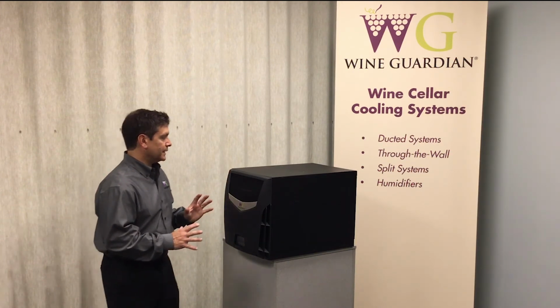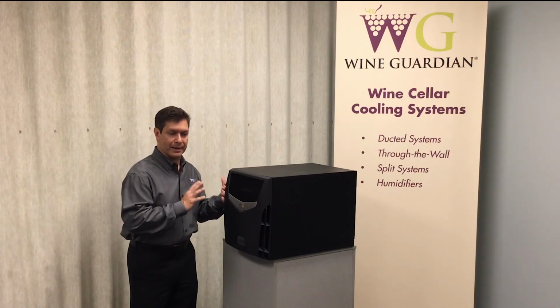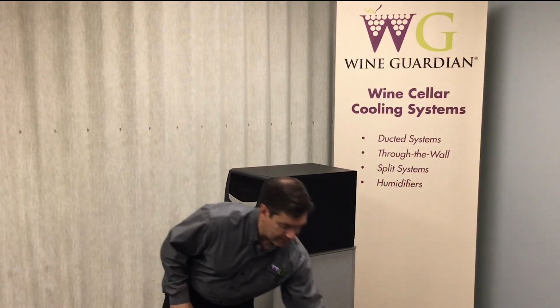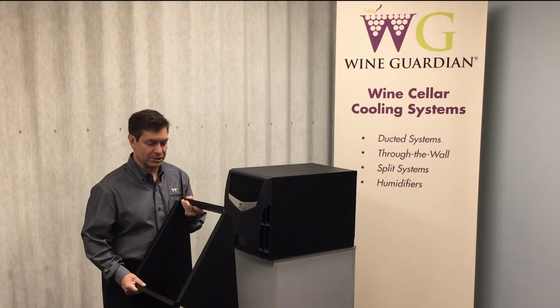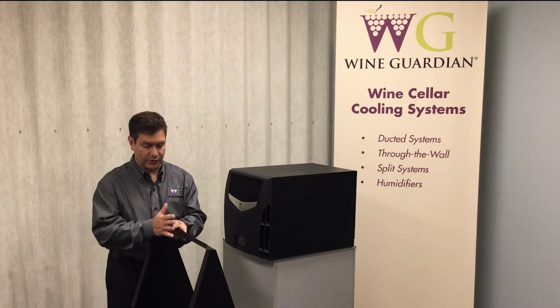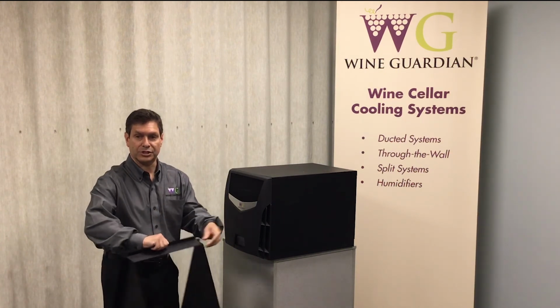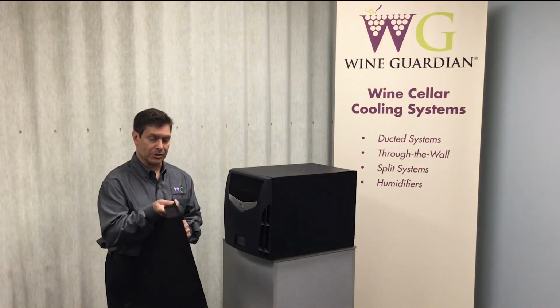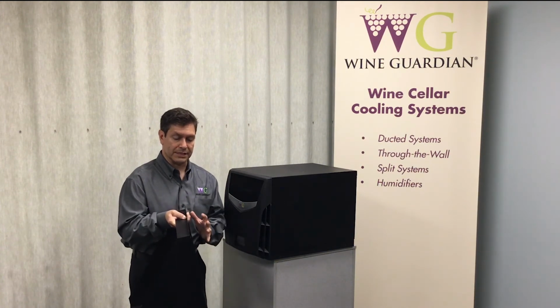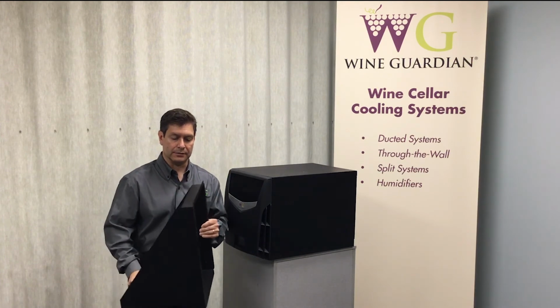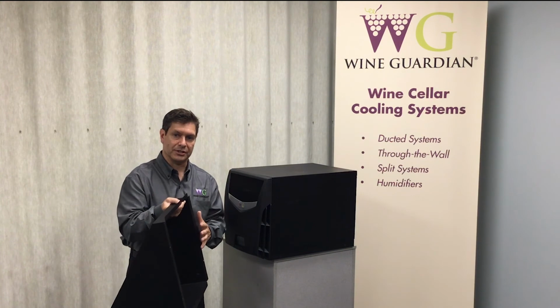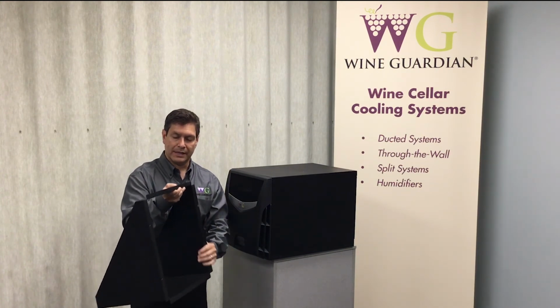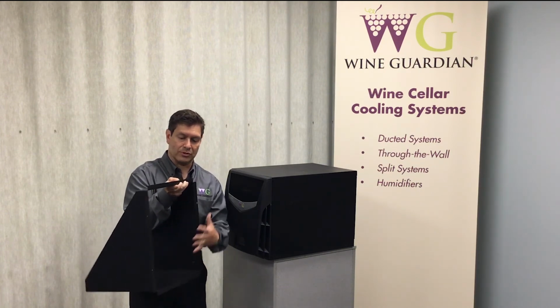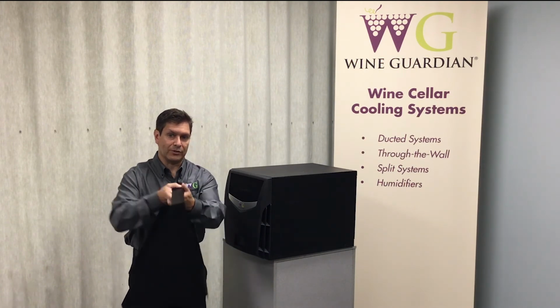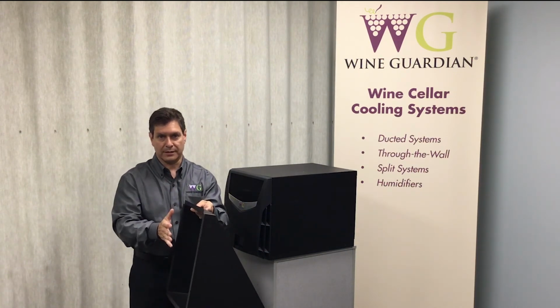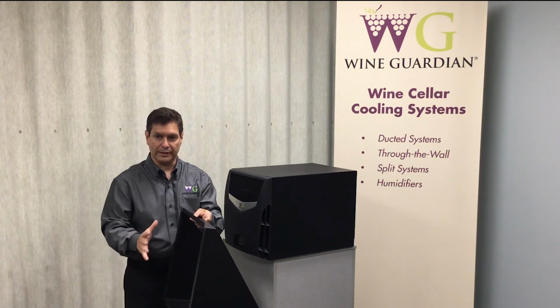Essentially, you have the ability to adjust where this unit is mounted inside the wine cellar by moving it along the length of the unit through the easy mount installation sleeve. So you could make it flush with the wine cellar side, or you can make it flush with the warm air side of the unit. Now understand that depending on which side of the system you want flush, you're going to have to move this easy mount sleeve around, so the flange is on the flush side. So you can see the flange around this easy mount sleeve. This is essentially where the flange would be mounted if this were a flush side application. If you wanted it flush on the wine room side, flip this around so the flange is on your wine room side. And then you can adjust how you place the wine cooling unit through the sleeve.